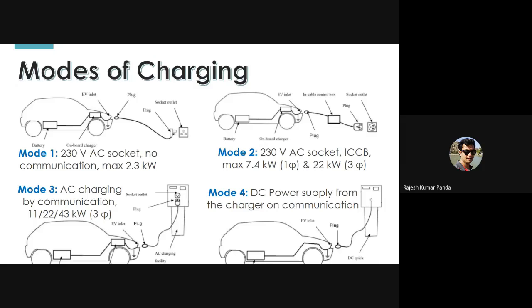In mode 1, that doesn't work, since there is no communication, so whatever power is available will go to the vehicle, and if it is something extra, it gets wasted. In mode 3, AC charging happens only via communication, and the range has gone up to 43 kilowatt. So this kind of mode 3 charging station is allowed in public places because the safety concern is taken care of.